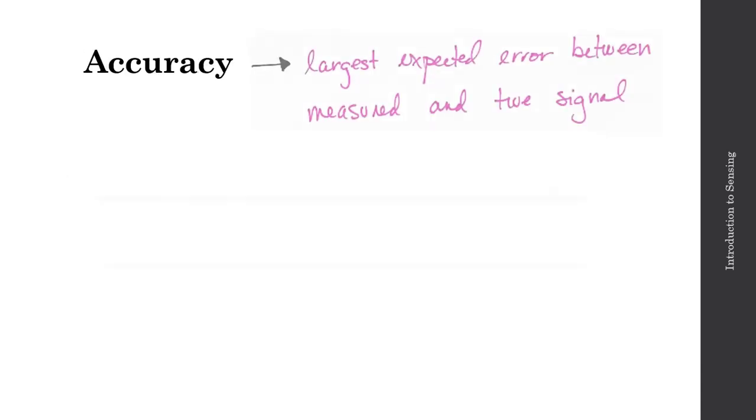The accuracy of your sensor is described as the largest expected error between the measured signal and the true signal. So the error E, that'll be the measured value minus the true value. And typically, we're taking multiple measured values and comparing that to the true. So there is some statistical nature to this error.